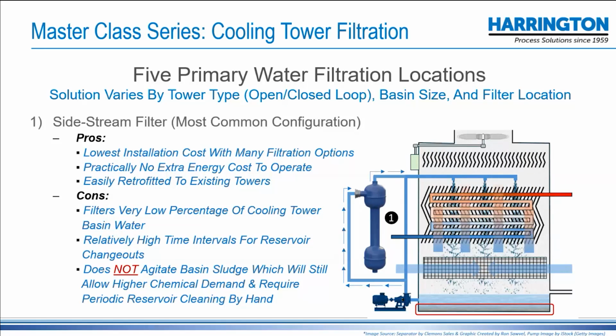But then, of course, as I already described, it's a very low percentage of water being actually treated, and it's not being filtered, it's just being separated. And it takes a long time to change out all of the water in the reservoir. It really doesn't do anything to reduce blowdown because you're still collecting solids in the basin. So I hope I'm not sounding too negative. It's just this is probably not the best place to filter your cooling tower.